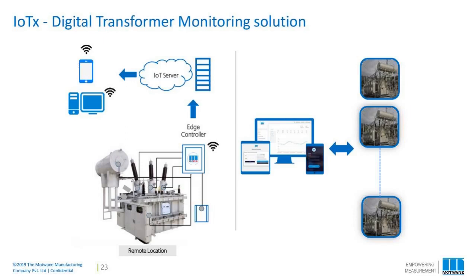But again, out of the box, the device does not necessarily need a new set of OTI/WTI. In the case that it does, it's very easily available and can be replaced. And when it comes to the oil level indicator, which typically would be a float sensor, even that can be integrated into the transformer monitoring device quite seamlessly. You may not even necessarily need an additional sensor for that - it depends on what the sensor is when we physically look at the transformer itself. So to answer your question, the integration doesn't necessarily need a new sensor, but it can work with existing sensors given the right type of output is available.